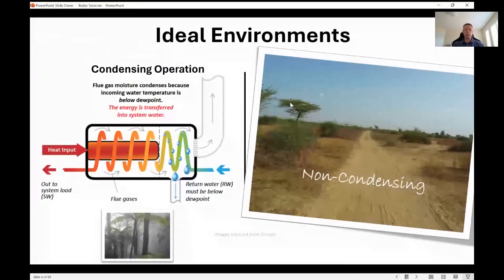Now, if you took a condensing boiler, hopefully, and you put it into that condensing situation where you do want to apply it, that return water temperature, that cold water comes in, and usually it'll enter a section of the boiler away from the burner, usually because it's too hot near the burner, where most of the condensation will occur. So if you're looking at this one here, it would enter in the back there, and there'll be an area that's not exposed to that burner. And that's where you're going to get all that condensation to occur. Basically, you're going to be pulling that heat out of the stack there. That water vapor is going to condense. It's going to go from a gas to a liquid. It's going to release a bunch of energy, and you're going to put that into your thermal balance. It then goes through, you get close to the burner, and you're not going to get a lot of condensation occurring where the burner is. It's just too hot. Then, of course, you go out to the system.